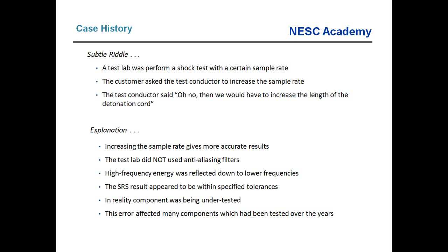So the accelerometers were picking up this high frequency energy, and after that data was digitized, that high frequency energy was reflected down to lower frequencies. And the SRS appeared to be within the specified tolerances, so the plots looked good and everyone was happy, but in reality, the component was being under-tested. And unfortunately, this error affected many components which had been tested for many customers over a period of many years. And it created a huge stir in the testing community.